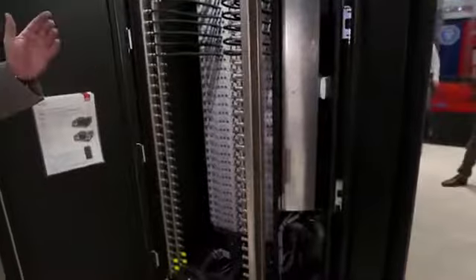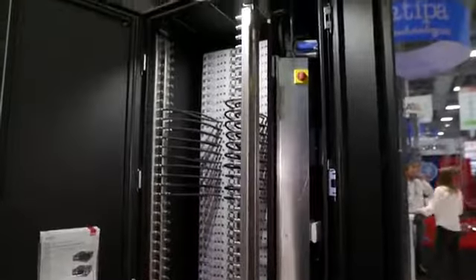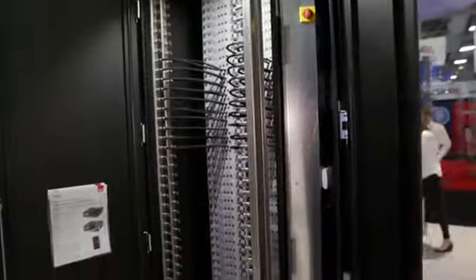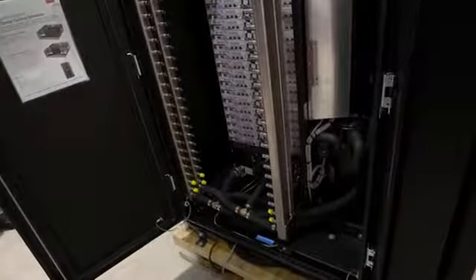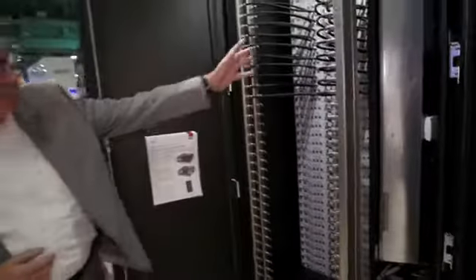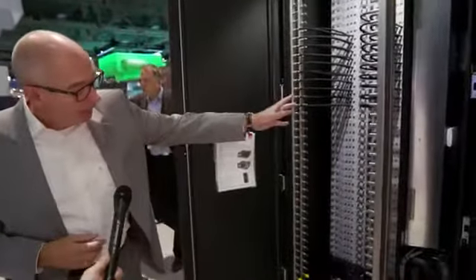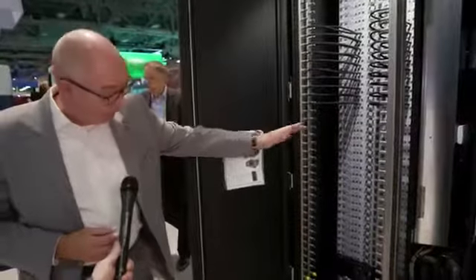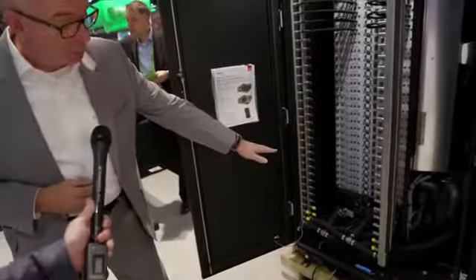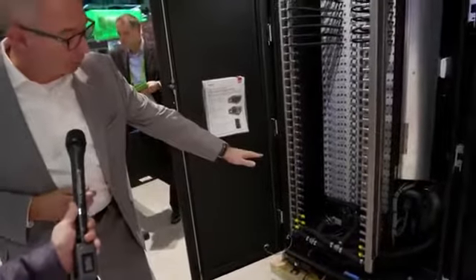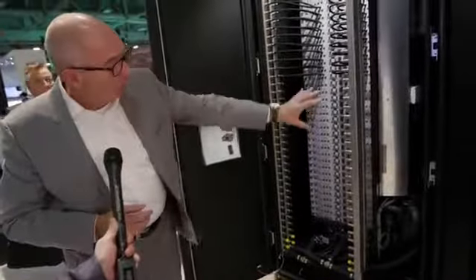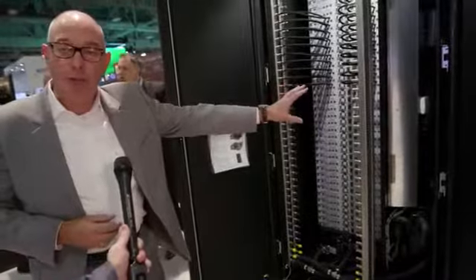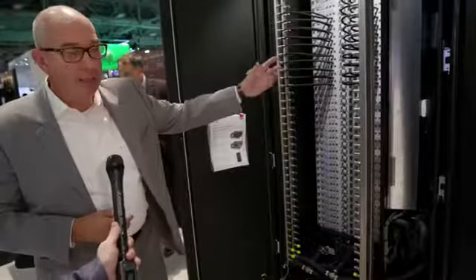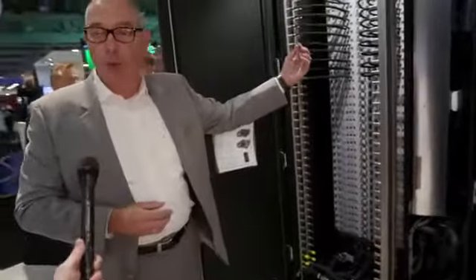What we see here is our first micro data center, and it combines the story of chip to atmosphere in one tiny box, meaning we have introduced liquid cooled servers and the elements from CoolIT here, the manifold system. On the bottom we have the coolant distribution unit that Jeff explained earlier, and on the side we have a cooling unit fully integrated that takes care of the remaining air-cooled part of the overall system.